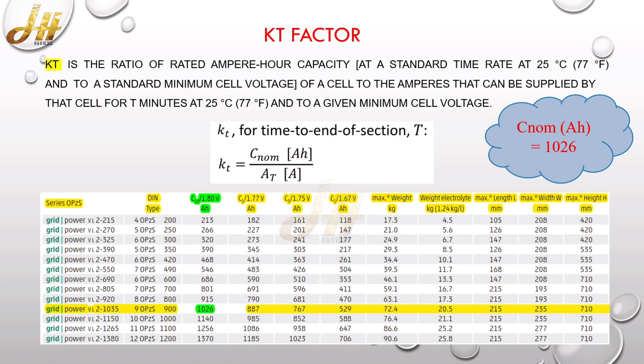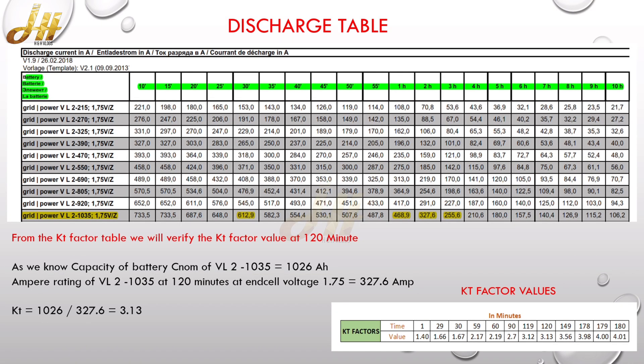So for the further calculation, we will use 1026 as the nominal capacity of the battery. Now to calculate the KT value, we need to have the value of the ampere that can be supplied by that cell for T minutes. So this can be derived from the discharge table which the manufacturer provides.